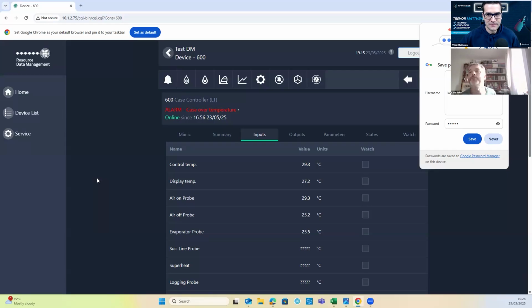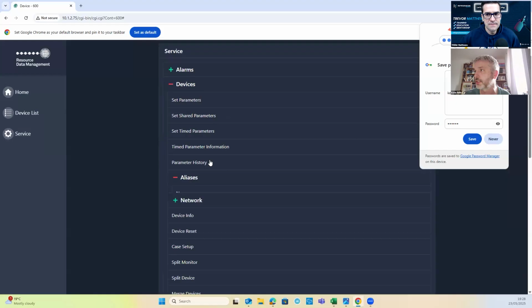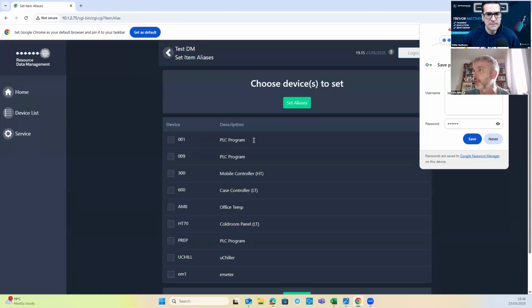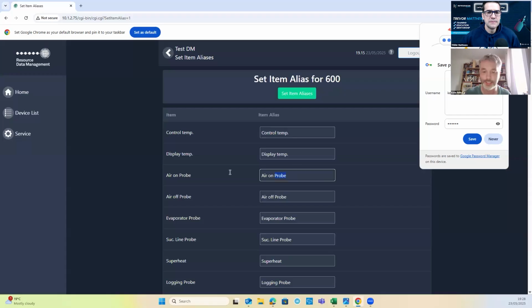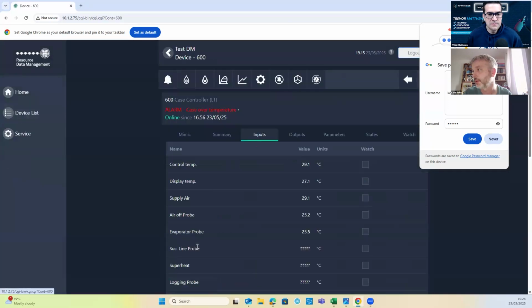And it's worth saying, and good point you make about the probe settings and what people call them, you can, through the data manager, change the names of all of these. You can go into aliases in here and change the names of any parameter you like. So let's have a quick look while we're at it. So I'm on controller 600, and I can just change the name in here. I can call that Supply Air. And then when I go back into the controller, that now says Supply Air. And we can do that with any item. We can do that with any input, any output, any parameter, and any alarm.